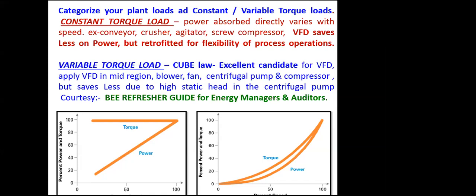So the constant torque loads, the production machines, want the VFD only for flexibility of process operations. It has nothing to do with energy savings there. The energy savings are possible only on the variable torque loads. You can see the variable torque load graph, where torque versus power are in sync. If you can give the optimum torque and the optimum power from the motor for the given speed, there lies the real crux of the energy loss. This energy loss can definitely be probed, studied and improved upon. Once you do that for variable torque, you must decide what measurements are to be done, and what measurements are to be done on the constant torque loads. These inputs will definitely give you appreciable energy savings, especially based on the cube law. It's an excellent candidate for VFD, and this will give excellent energy savings on these variable torque loads.